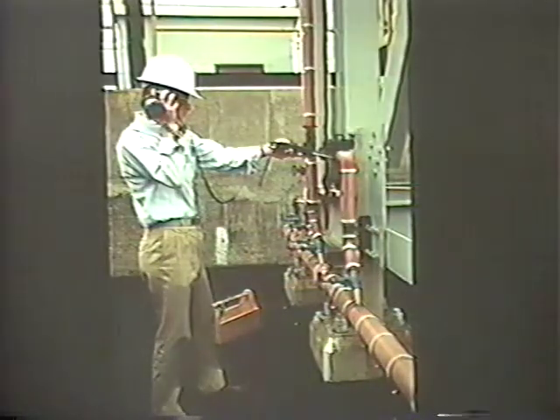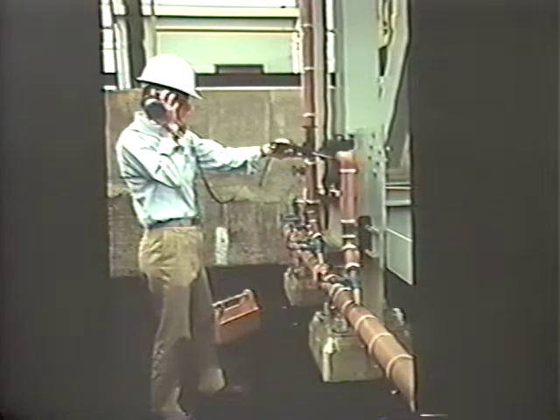The traps in the steam system are checked periodically. In a recent audit, 64 traps out of 155 checked were not properly working. One trap blowing continuously cost about $400 a month. Heat traces help prevent liquids like water from freezing. Insulation prevents heat loss. This pipe lacks the proper insulation and has a major leak as well.